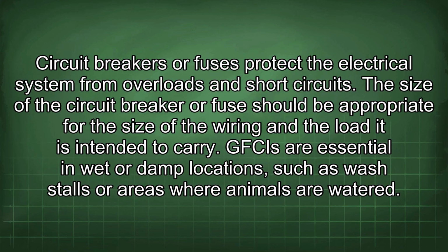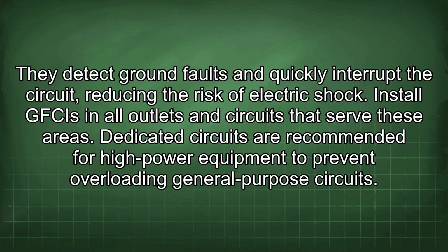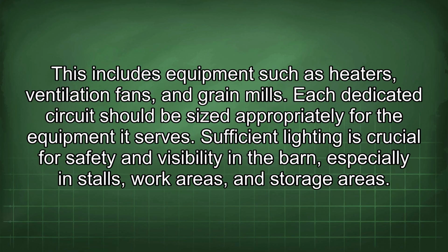GFCIs are essential in wet or damp locations such as wash stalls or areas where animals are watered. They detect ground faults and quickly interrupt the circuit, reducing the risk of electric shock. Install GFCIs in all outlets and circuits that serve these areas. Dedicated circuits are recommended for high-power equipment to prevent overloading general-purpose circuits. This includes equipment such as heaters, ventilation fans, and grain mills. Each dedicated circuit should be sized appropriately for the equipment it serves.